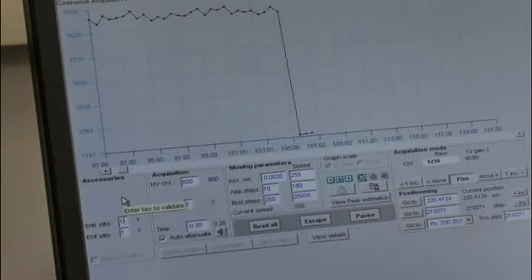Another thing we can do here is manually change the slits. The entrance slit, I'm going to make that smaller. If I make it smaller, my signal should drop off, because now it reduced the amount of light coming into the box. If I make the exit slit larger, it should increase the signal.